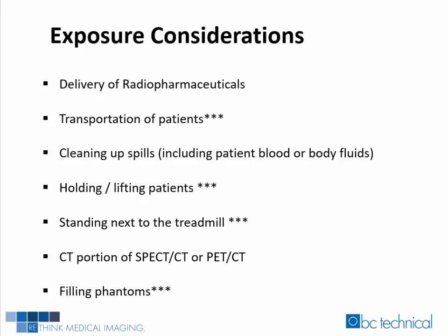Filling phantoms: make sure you wear ring badges when filling phantoms. Filling phantoms for QC or ACR can be time intensive. Phantom mixing can be a source for high ring badge readings. To mix the phantoms, consider placing absorbent paper on the floor and rolling the phantoms back and forth with your foot.